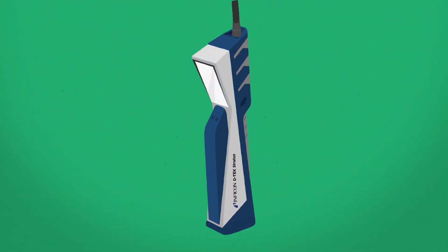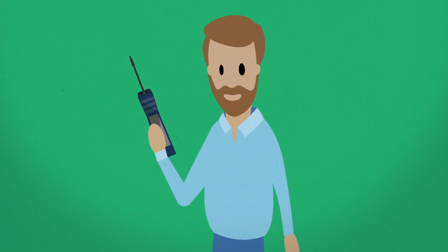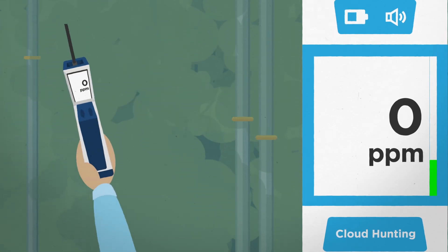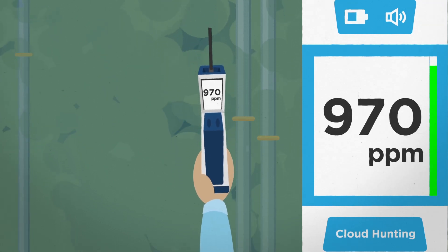Now there's a better solution for refrigerant cloud hunting. Introducing D-TEK Stratus Refrigerant Leak Detector and Portable Monitor. The revolutionary D-TEK Stratus guides you to the leak source through an easy-to-follow numeric parts-per-million readout. The PPM readout indicates the refrigerant concentration — the higher the number, the closer you are to the leak source.